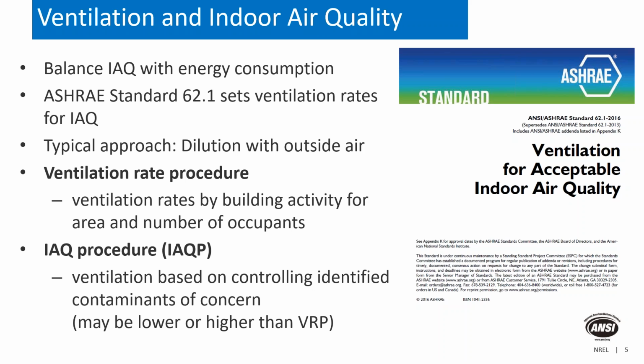So that assumes that your pollutants are inside, right, not outside. We can filter outside air. Typically we do for particulates, but that's about all we filter out of the outside air. So 62.1 has a ventilation rate procedure where they specify ventilation rates by different building activity for area and the number of occupants. So that's kind of the default method. If you don't do anything else, you should follow the ventilation rate procedure.